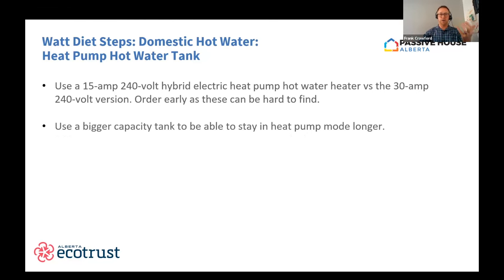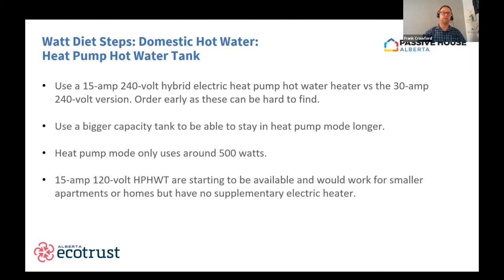Other tricks when you go to this heat pump hot water tank is you want to use a bigger capacity tank. So probably almost always buy an 80 gallon tank. That way it can stay in the heat pump mode longer. The advantage is that heat pump mode only uses about 500 watts of electricity versus electric resistance, which uses either 3600 watts for the 15 amp version or 7200 watts for the 30 amp version.